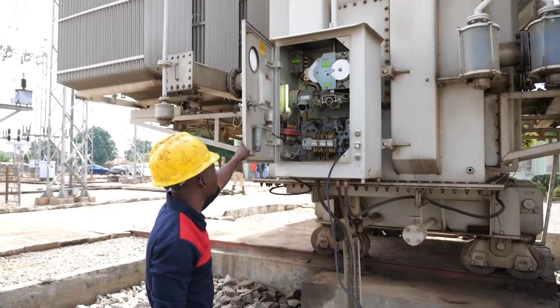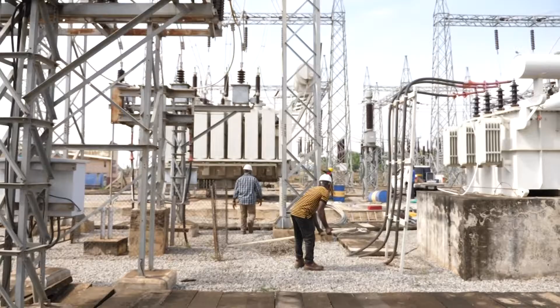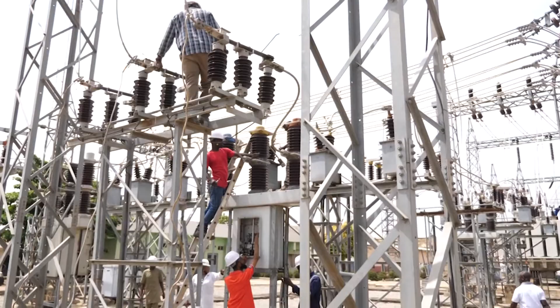That is, the energy comes in on 330 kV voltage level, and the transformer steps it down to 132 kV voltage level. Then it's now interconnected to another 132 kV 33 transformer in that same substation. That transformer will take the input on the 132 and step it down to 33. Then the outgoing feeders now is the line, power line going straight to the distribution injection substations. So what it means is that the 33 kV outgoing feeders I mentioned are the lines that are available for Abuja Electricity Distribution Company to take energy from.